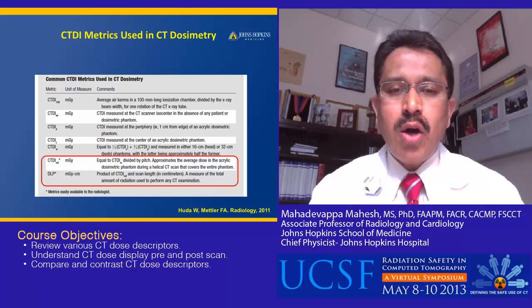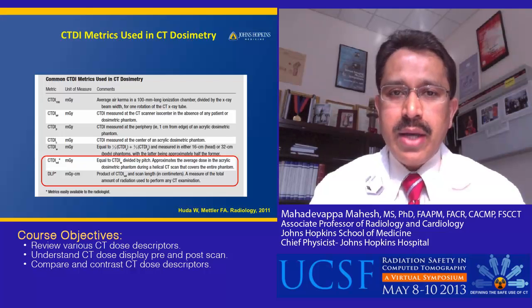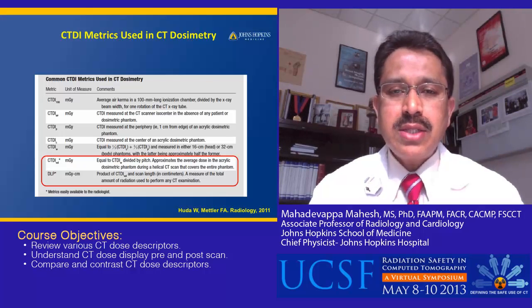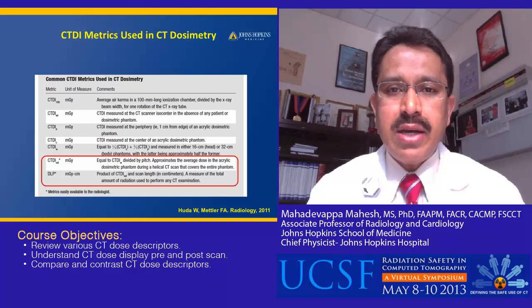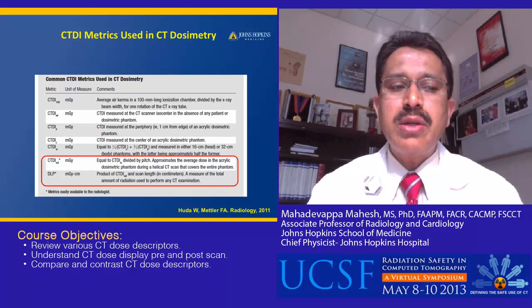These are the common CTDI dose metrics used in CT dosimetry. However, as of now, the key dose descriptors are confined to the last two: CTDIvol, which has a unit of milligray, and DLP, the dose length product, which has a unit of milligray-centimeter.